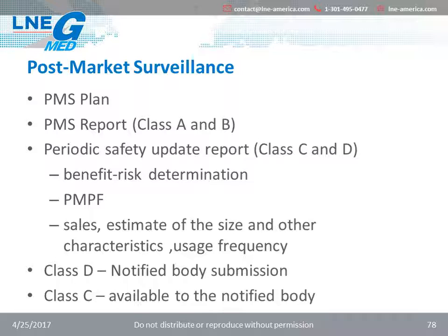Manufacturers of Class C and Class D devices must prepare a periodic safety update report. This report must also include the requirements of the PMS report. However, it must also include the conclusions of the benefit risk determination, the main findings of the post-market performance follow-up, the volume of sales of the device, and an estimate of the size and other characteristics of the population using the device, and where practical, the usage frequency of the device.